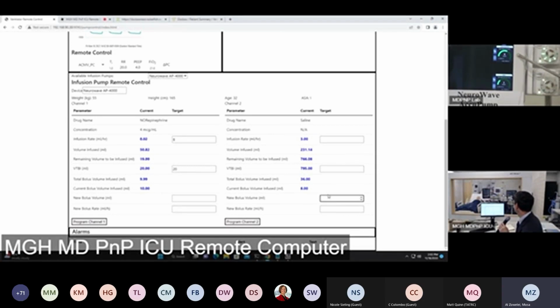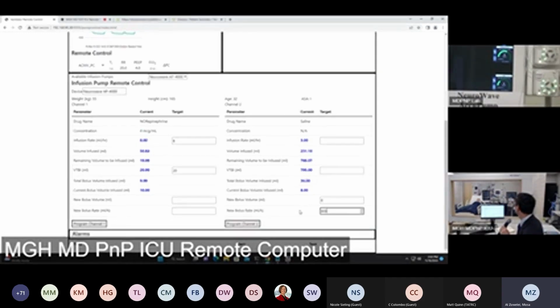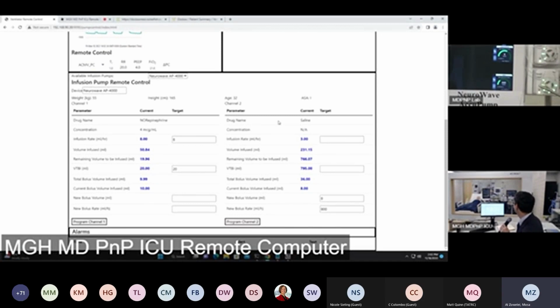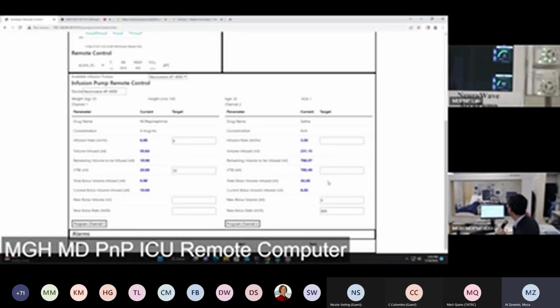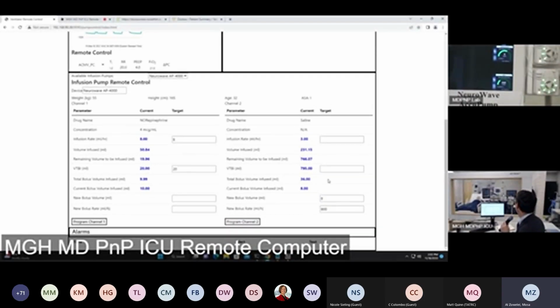And I'm also going to give a small fluid bolus. It seems like a good idea to me. So I'm going to do a bolus of 8 milliliters so that it's very quick for this demonstration. I'm going to do that at a rate of 800 milliliters per hour. So it's only going to run for a few seconds to give that 8 milliliters. So I click Program Channel 2, and we see the pump mechanism start to spin much faster. It's just had a huge increase in rate. And it's going to count down the amount that it's infused, and we'll see that on our remote display, and it'll automatically stop after it's delivered that entire 8 milliliters.